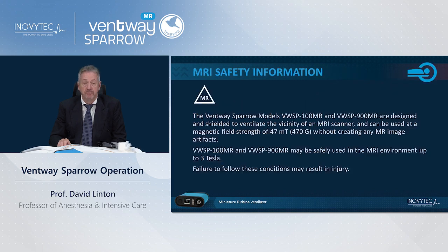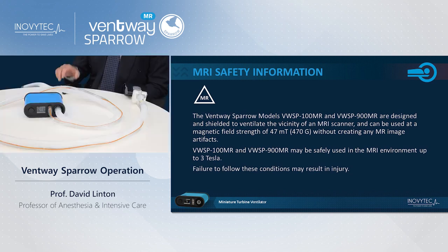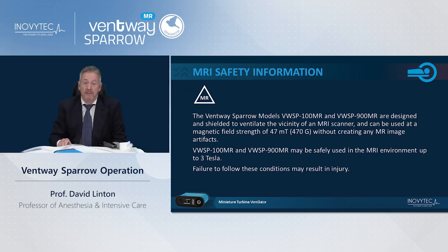I want now to address the use of the Ventway Sparrow MRI approved ventilator, identified by its blue color, in the MRI scanner. Note, the Ventway Sparrow models, the 100MR and 900MR, are designed for use in the MRI scan to ventilate the patient in the vicinity of the scanner, shielded, and can be used at a magnetic field strength of 47 mT and 470 G without creating any MR image interference. Note the MR indicates that it's magnetic resonance approved, so the 100MR and the 900MR may be safely used in the MRI environment up to 3 Tesla.